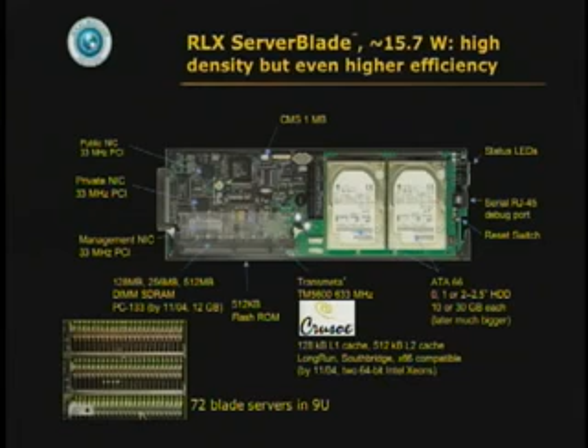So Dr. Feng at Los Alamos put 240 of those blade servers in one cabinet, and he ended up with 5 square feet of floor, 3.2 kilowatts of load. That's like 2 hair dryers. It's 8 times denser, but close to 8 times less power than the Wintel solution. 160 peak gigaflops, 240 after an upgrade, and it gets very capable if you fully populate it. It had 100% uptime for 2 years in an uncooled, dusty hallway at 29 Celsius at high altitude where the air doesn't cool as well.